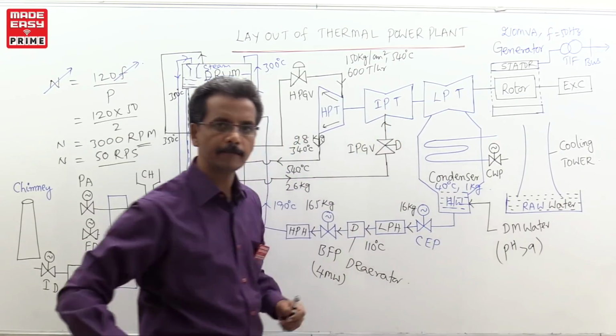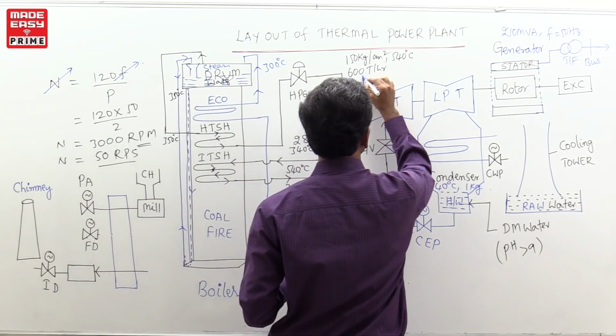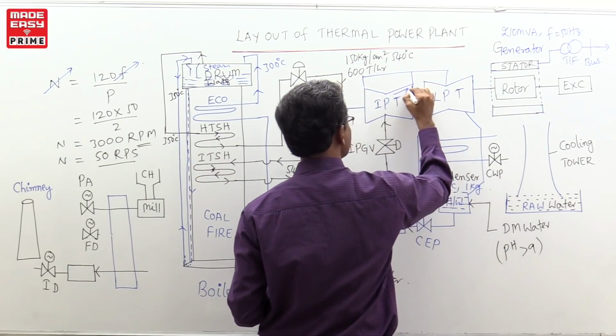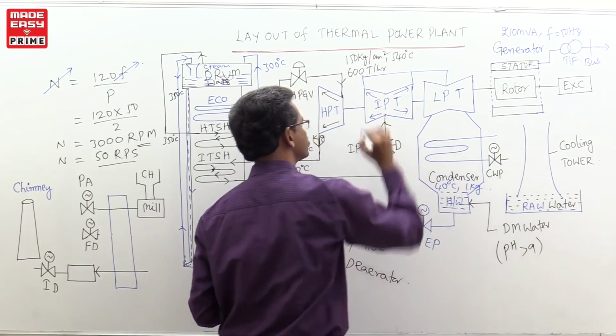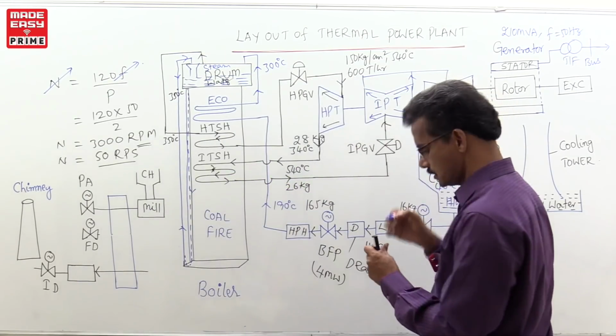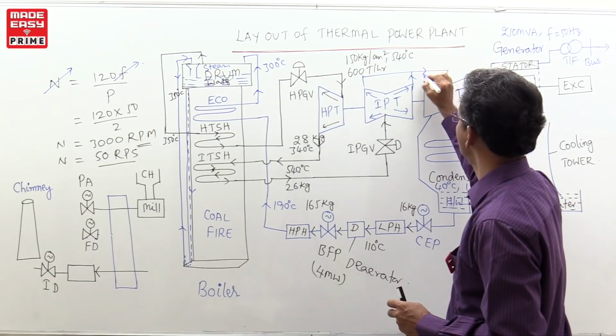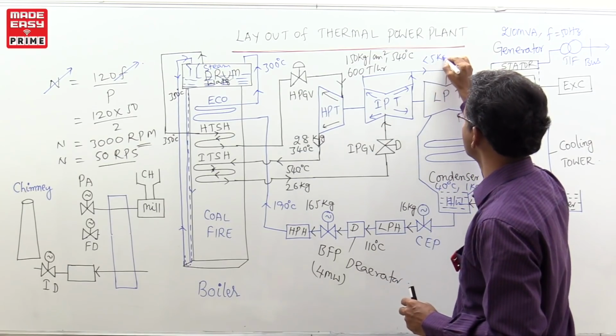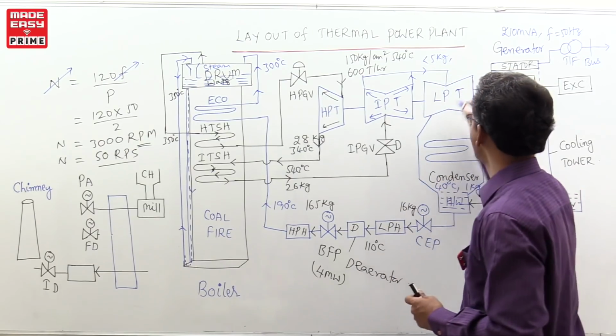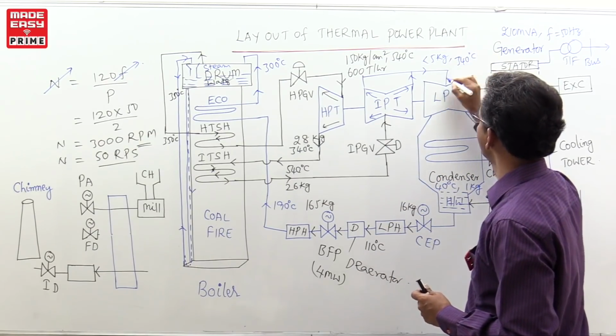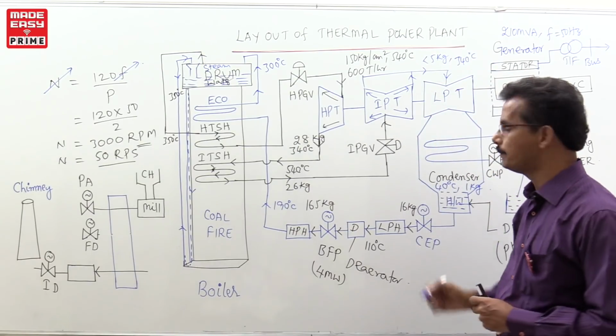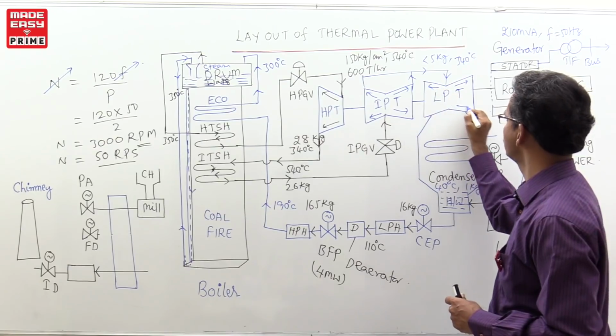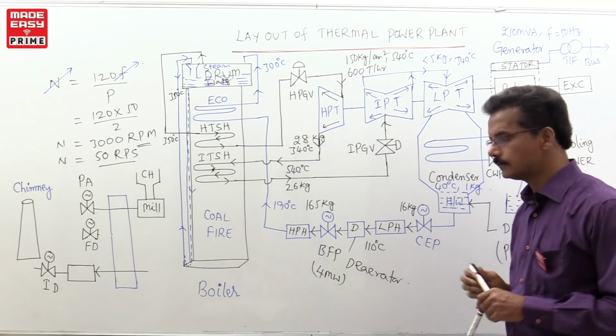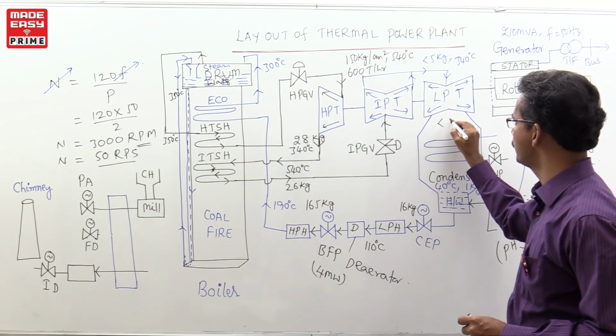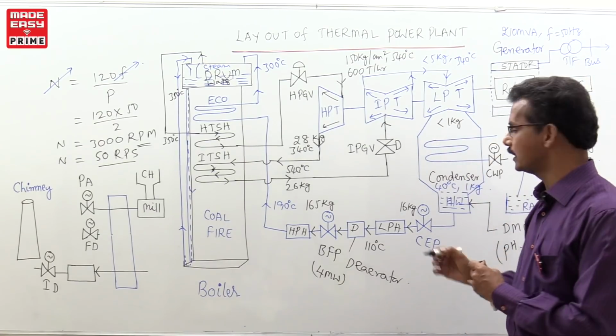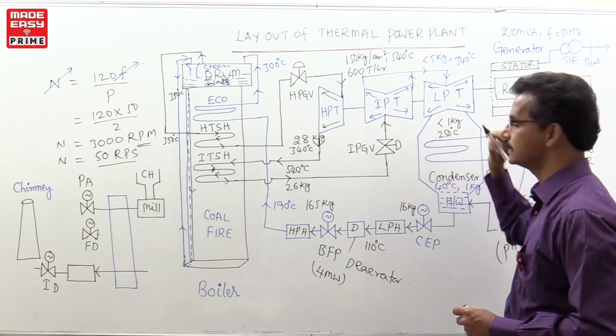Now, this is an IP turbine. After expansion of the steam inside this IP turbine, the steam parameters drop to a pressure of less than 5 kgs, around 2 to 3 kgs, and the temperature comes to around 340 degrees centigrade. Now, this steam enters the LP turbine, and here the steam will expand. When the steam is expanded, the pressure, and this is very important, drops to less than 1 kg, and the temperature is around 250 degrees centigrade.